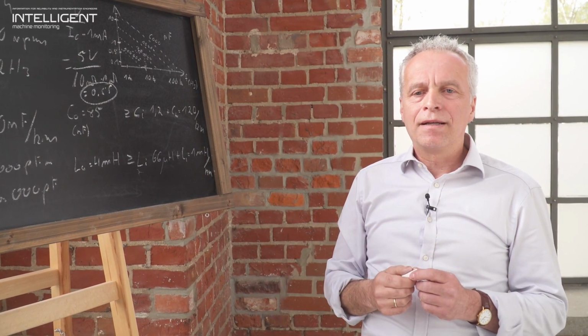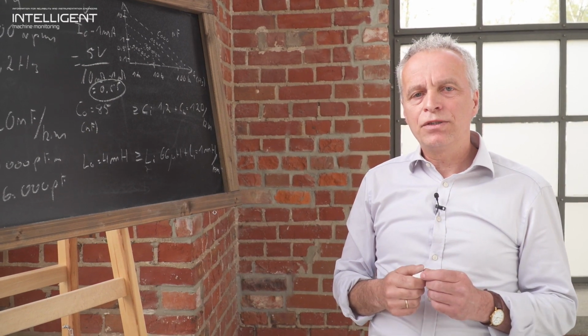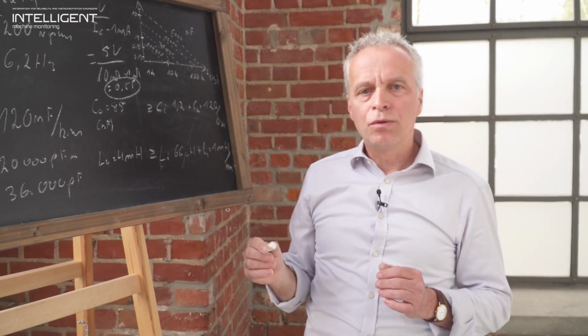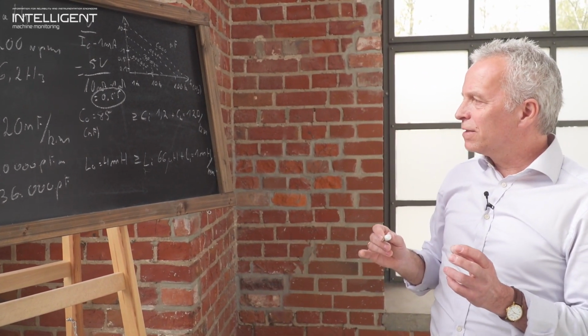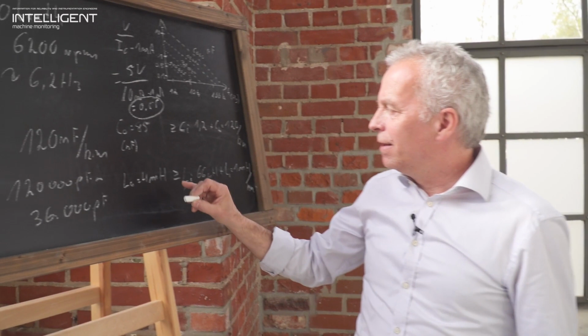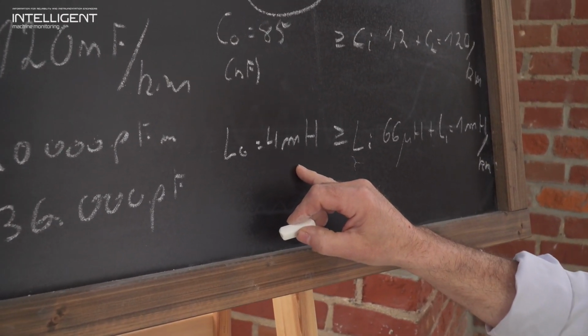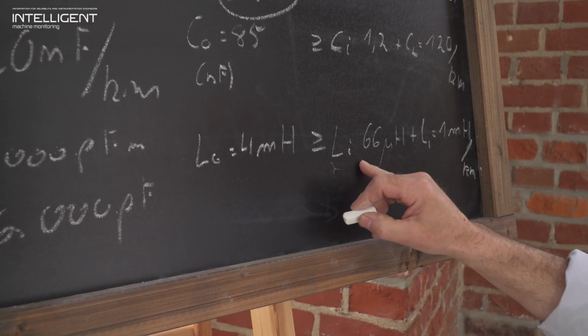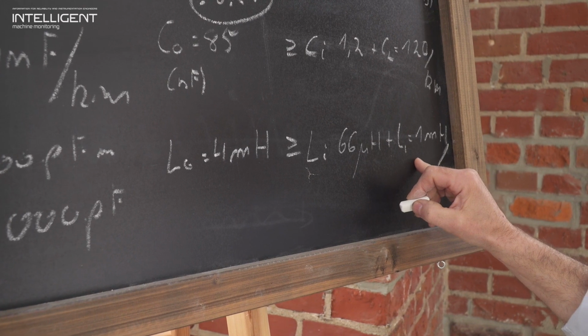This is done, for example, by barriers or galvanic separation units that limit the power going to the field, intrinsic safety. And the concept is that the inductivity of such an input card is greater than the sum of the inductivity of the sensor plus the inductivity of the cable.